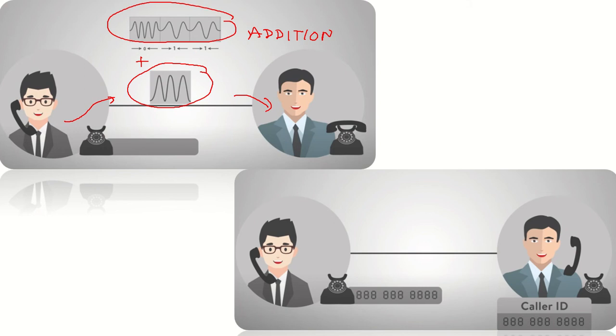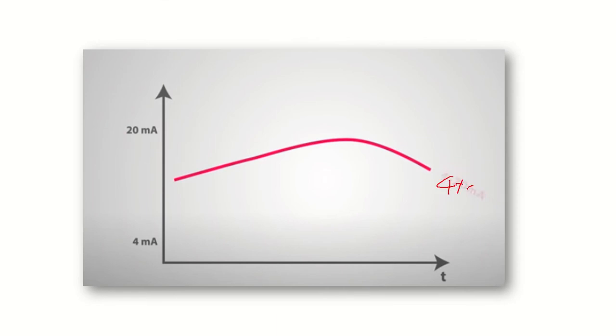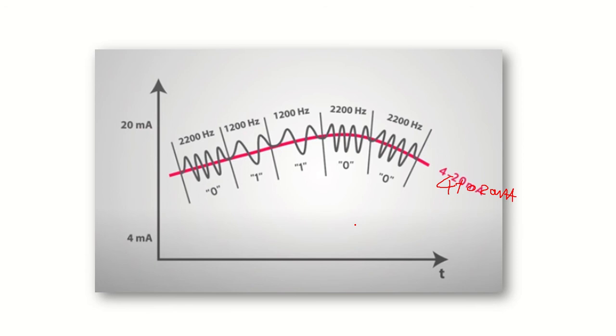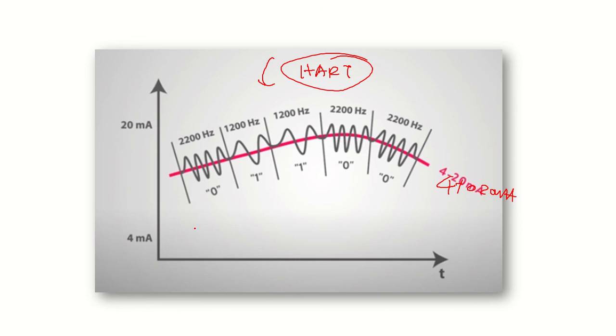The same scenario takes place in industry. We have the conventional 4 to 20 milliampere current loop, and if you add the Bell 202 modem standard to it, this signal is called the HART signal. HART is your analog 4 to 20 milliampere signal with a digital signal added on top. This digital signal carries information such as device parameters, operating conditions, and several other parameters. This way it increases productivity in industries — more information is sent via the same pair of wires.